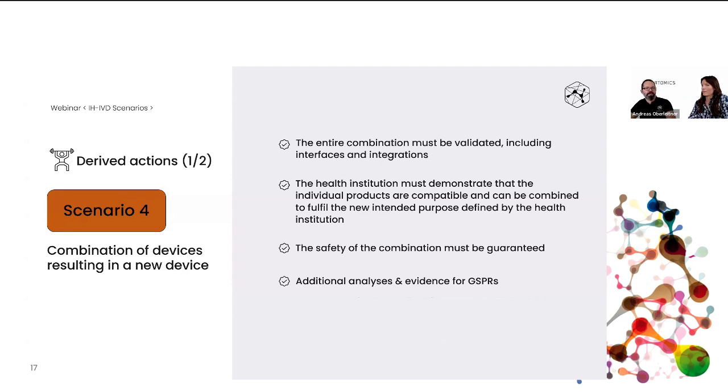So what about the scenario where the health institution combines devices that were originally not intended by the manufacturer? Yeah, this is the next one we discussed, our scenario number 4. If we are combining different devices, then I think it's pretty obvious that this combination needs to be safe and effective again, right? It's always the same thing, safety, effectiveness, the two sides of the scales, and we need to prove it.